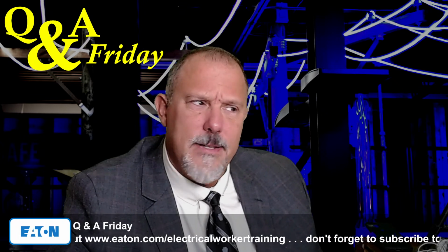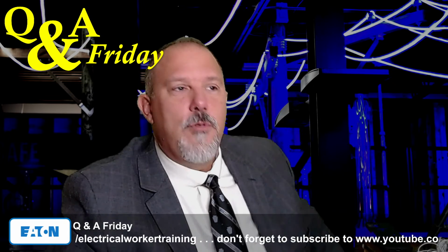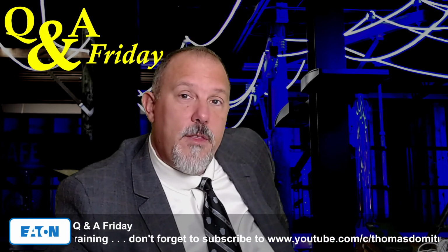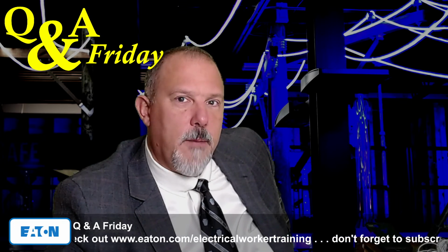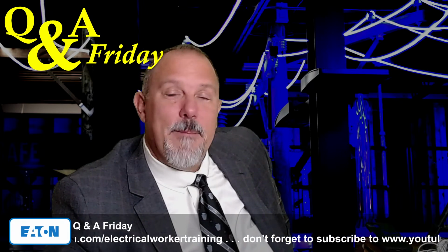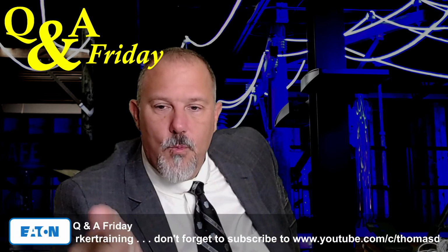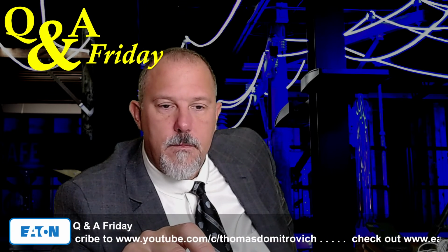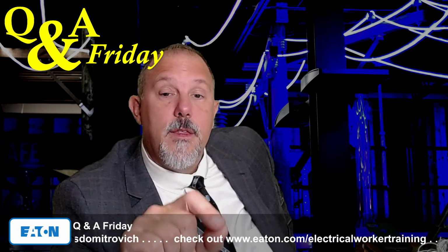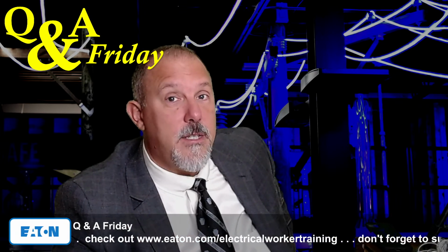I said, with what? And he says, I disagree with you when you say that the utility available fault current will always be greater than from the backup generation. He goes, I do some hospitals where the available fault current from the combined generators exceeds the available fault current from the utility. And I said, I wasn't talking about healthcare. So, and I'm sure it's not just healthcare. I think I would say, in general, it's not a safe assumption to say the available fault current from the generator will always be less than from the utility.